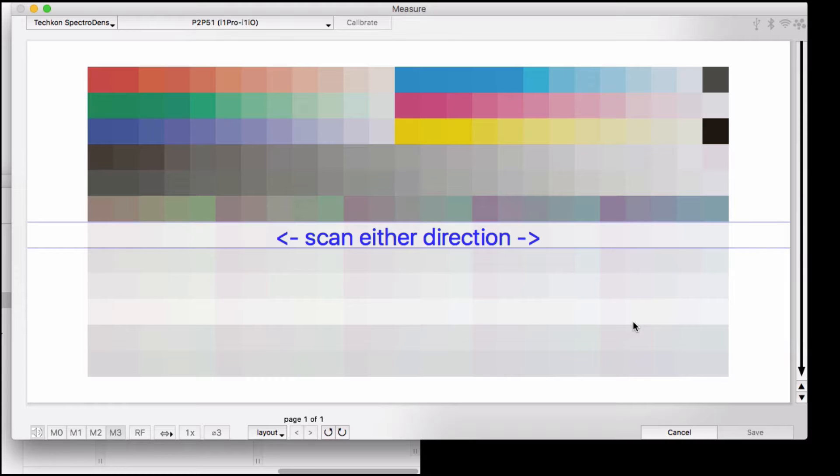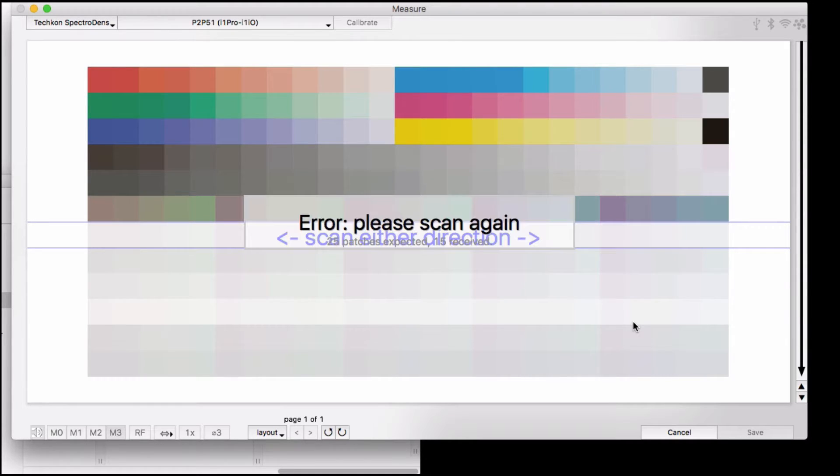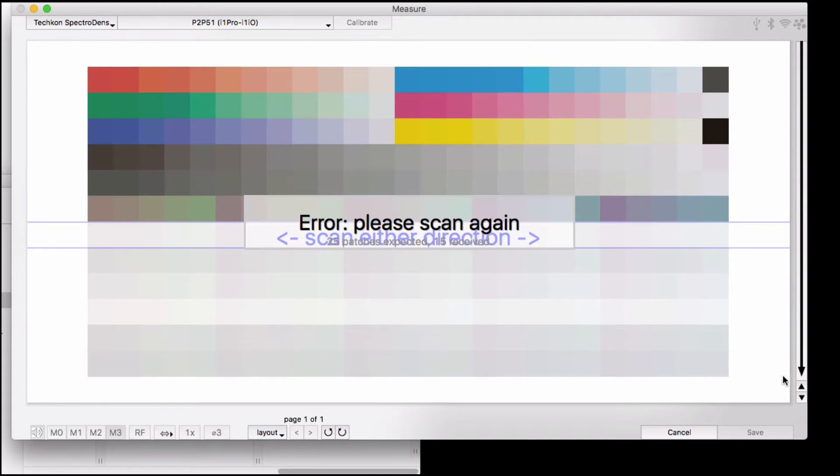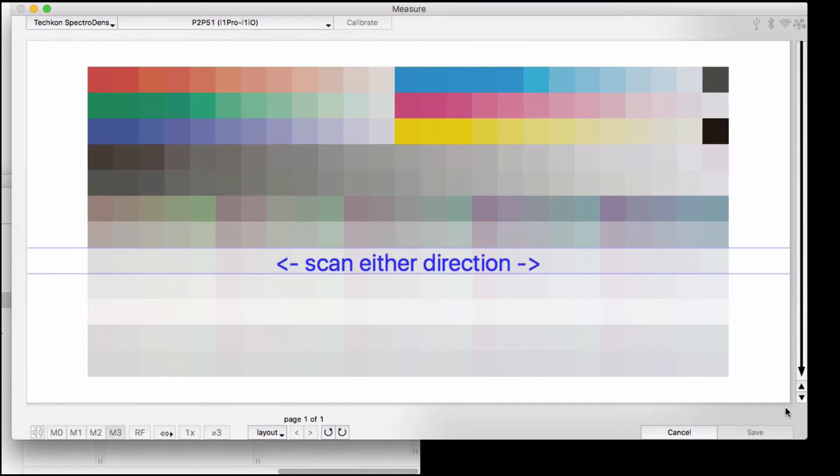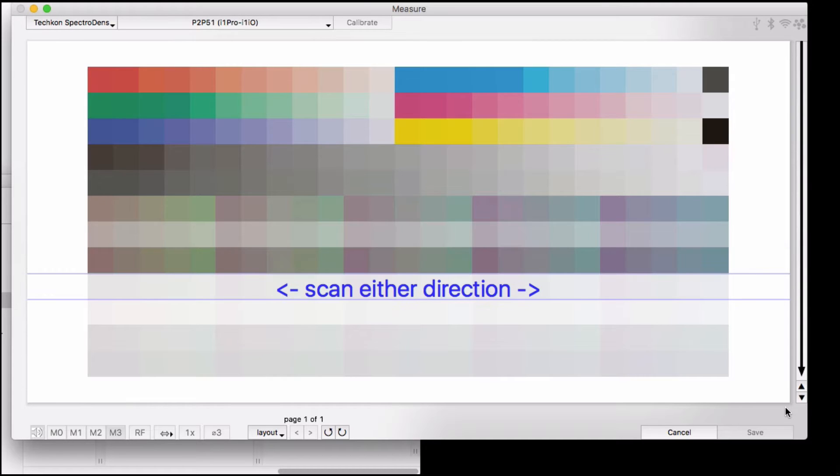If you make a mistake, you can use the arrows to step up to a previous row and measure again. Also note that the SpectroDens has a way of detecting if it thinks you made a poor reading, and it might stay on the row you just finished without advancing. So pay close attention to what's on the screen so you can be sure you're measuring the row you're supposed to be measuring.